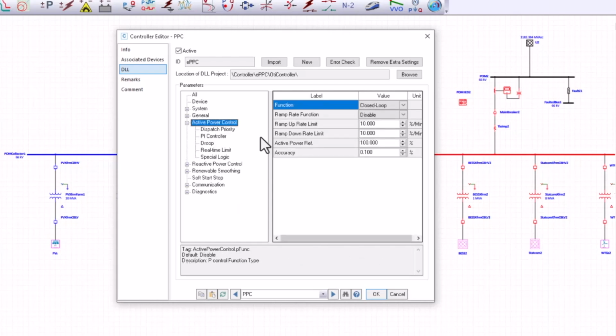Next, let's talk about the core functionalities of EPPC. First one is active power control. The active power control uses a PI controller to regulate active power at the point of interconnection. It also has a ramp rate limiter to control power changes at the POM. It supports a dispatch priority setting for hybrid plants. This becomes very important in hybrid plants where you want to dispatch different assets with different priorities. And it can also implement a droop-based frequency support which adjusts the output power during grid frequency fluctuations.